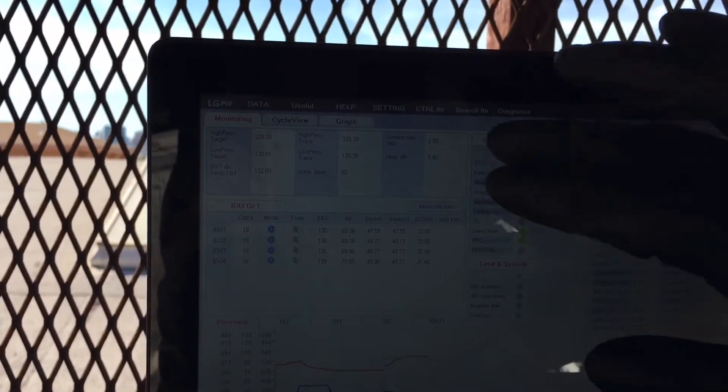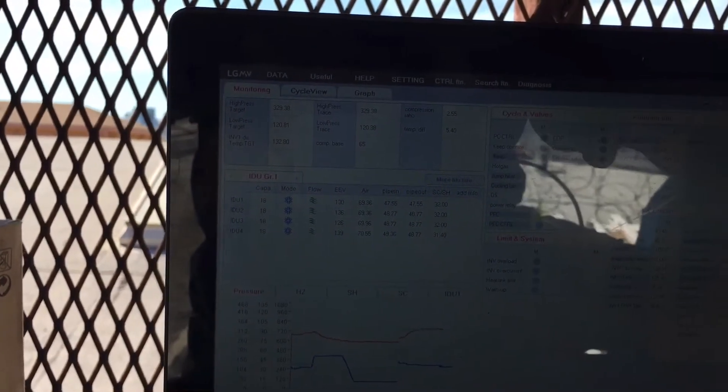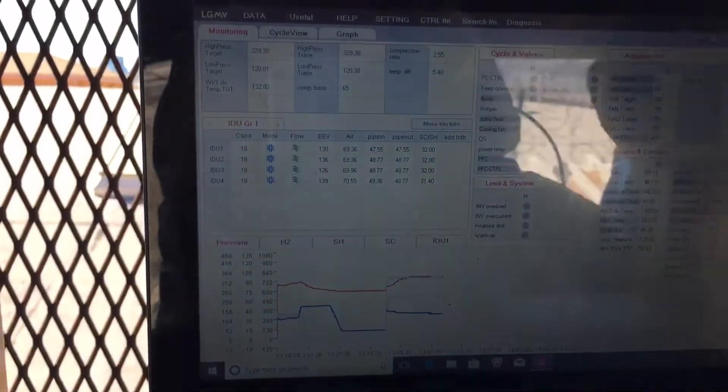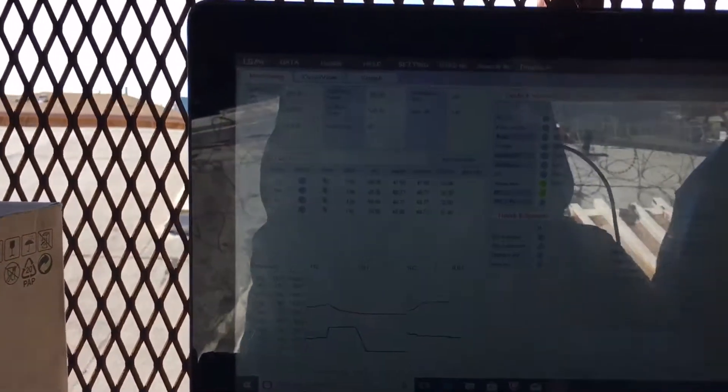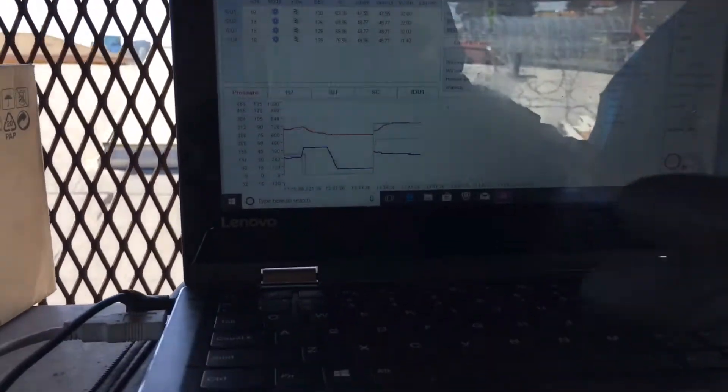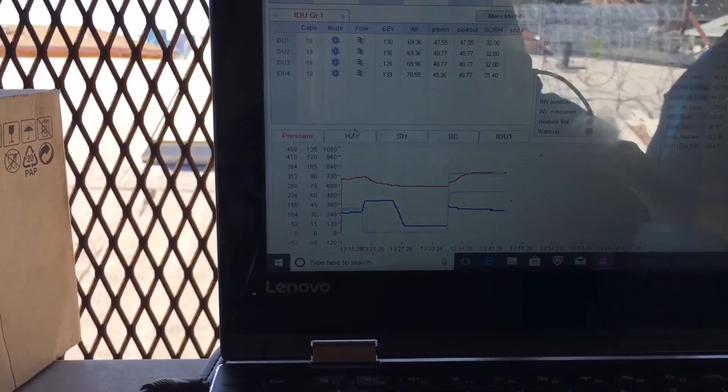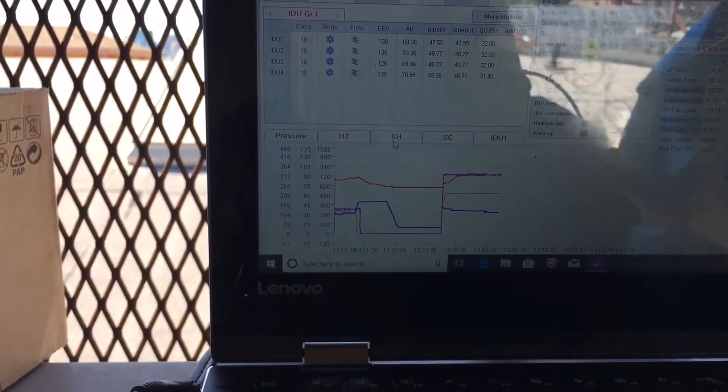Our compression ratio for you guys who like to do the measure quick and you want to go, we go all the way down and get your compression ratio. This thing's screaming balls to the walls because I have it set for 64 degrees and the room is around 70 degrees. So since it has that much of a temperature difference, it is overdrive. Let's go to, let's see our Hertz. Let's go down here so you can look at your Hertz. Here's your superheat.